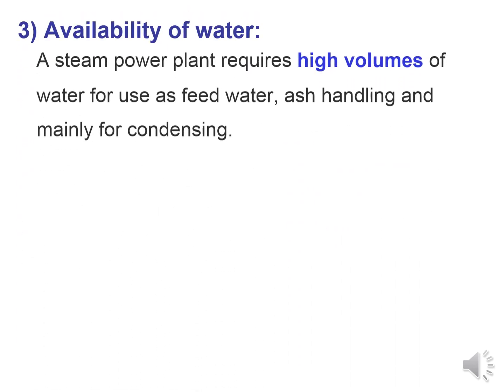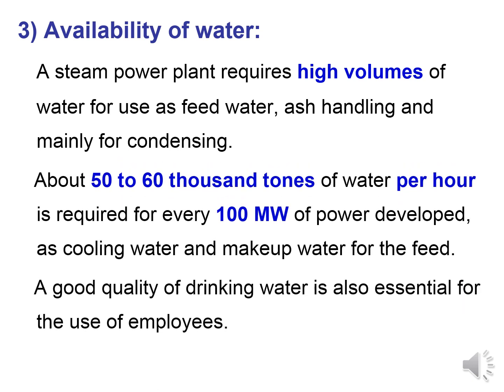High volumes of water are required for use as feed water, ash handling, and condensing. About 50,000 to 60,000 tons of water per hour is required for every 100 megawatt of power developed. We need a good quality of water for energy development and also for the drinking purposes of employees, as around 2000 people will be working in the steam power plant.